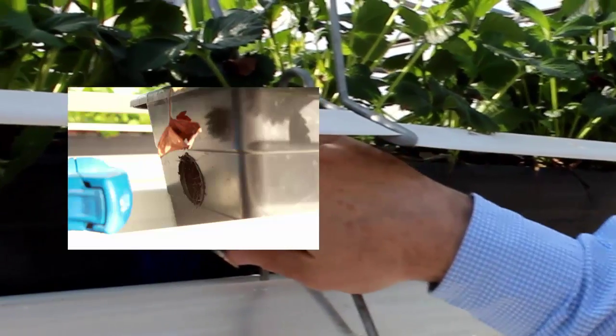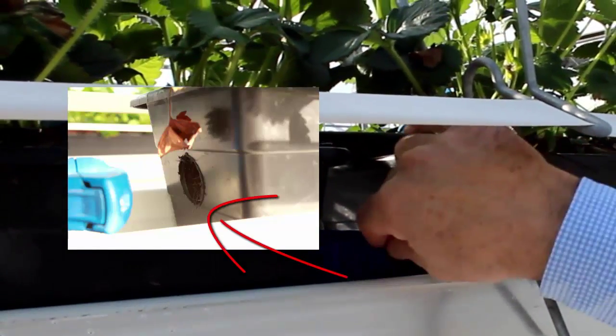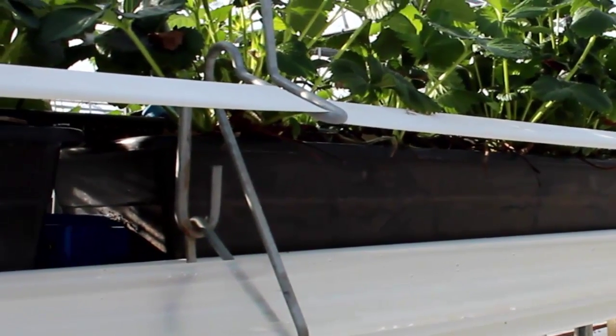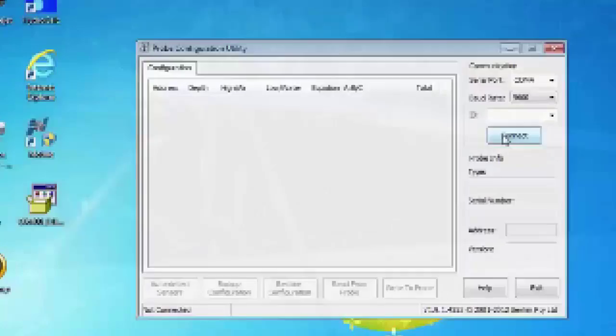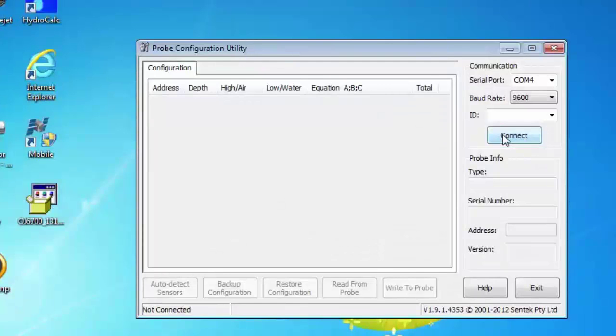So once you've cut the hole and augured out some coir, you can then insert the probe into this trough and you should be getting good readings. We've got the probe installed into the trough. What we now need to do is connect to the probe configuration program to check the sensors. I've got good contact with the coir.